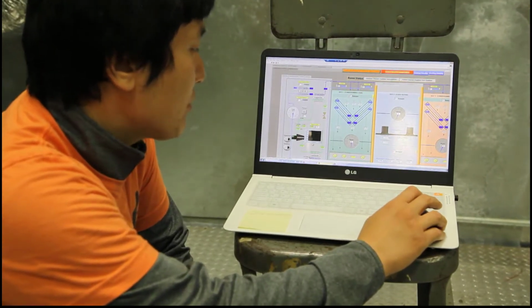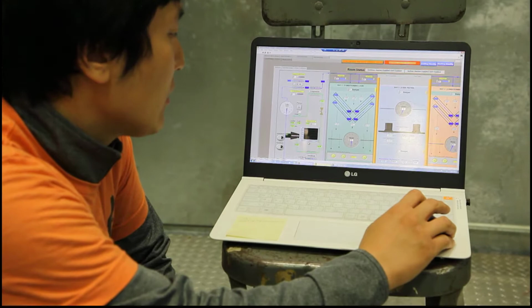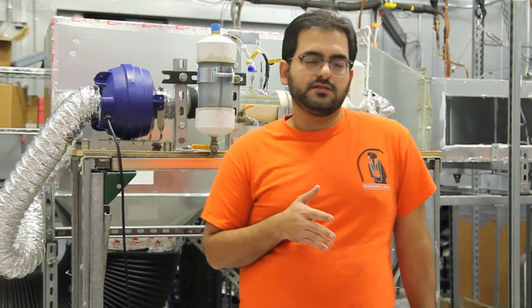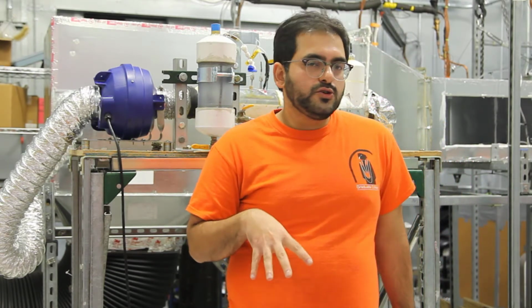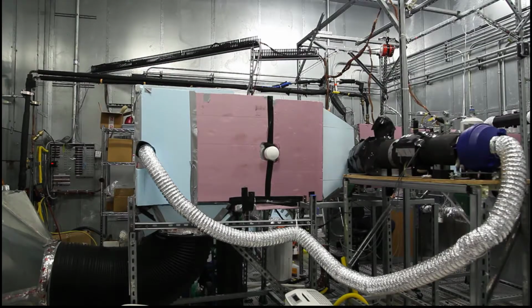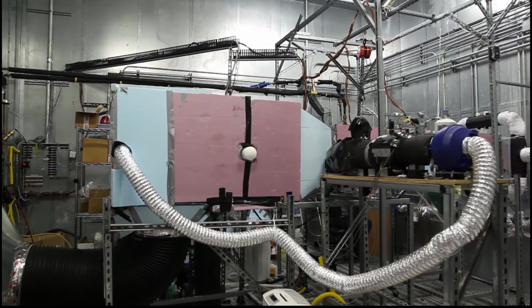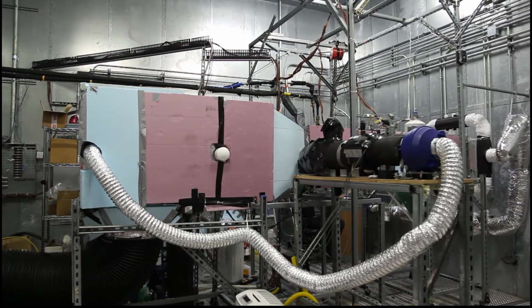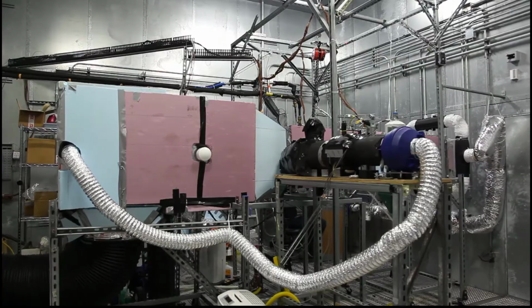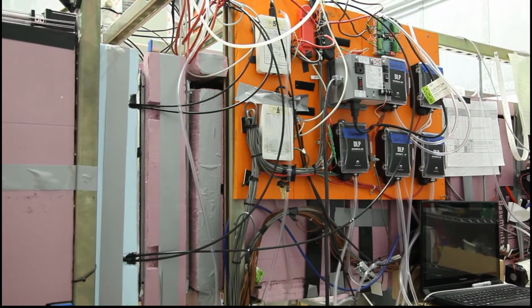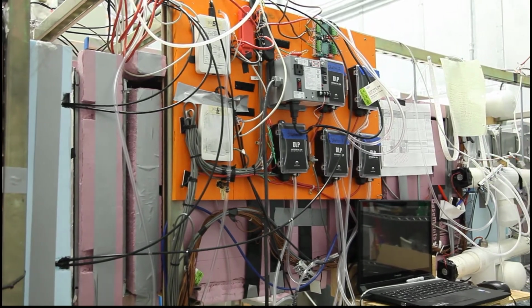So our facility has the capability to test units with a cooling capacity of up to 20 tons. It can cover relative humidity in both the rooms from 10% up to 90%. The outdoor room has the capacity to generate sub-zero temperatures, so we're talking about minus 40°F, and it can go up to 130 degrees Fahrenheit. While for the indoor room, where our requirements are not that stringent, we can still achieve between 50 degrees Fahrenheit and 100 degrees Fahrenheit. And we have an airflow circulation capacity of approximately 8,000 cubic feet per minute.